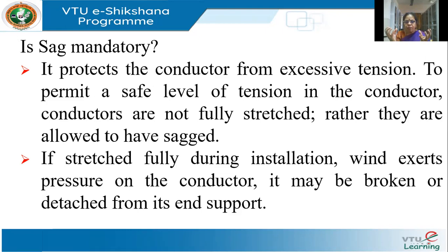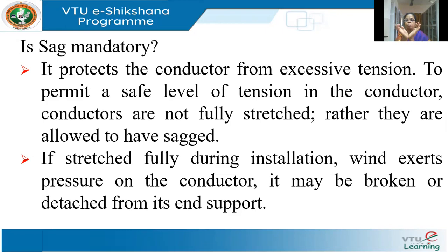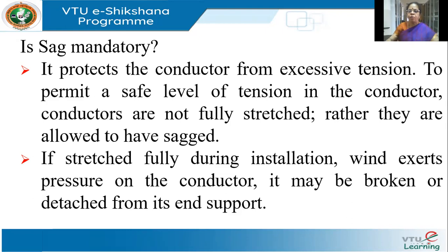We allow conductors to sag to protect them from snapping. When it is very tight and wind pressure acts on it, it will just snap. Whereas if you give a small sag it may swing — the whole conductor may swing and will not become detached from its support. So sag is mandatory for proper functioning; it is intentionally given.